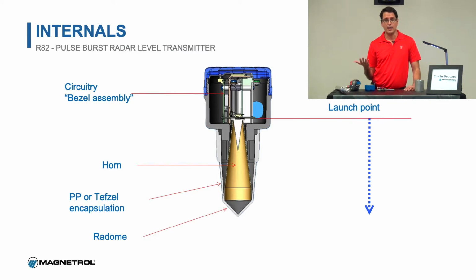Another problem with ultrasonics is steam. Any kind of steam in the process usually is very problematic for the ultrasonic wave to go through. With this being a radar, we're talking about an electromagnetic pulsed radar. It will cut right through that steam. It won't be an issue. Also for vacuums, if you're working in a vacuum, obviously ultrasonic is not going to work because sound doesn't travel through a vacuum, but the radar will work.